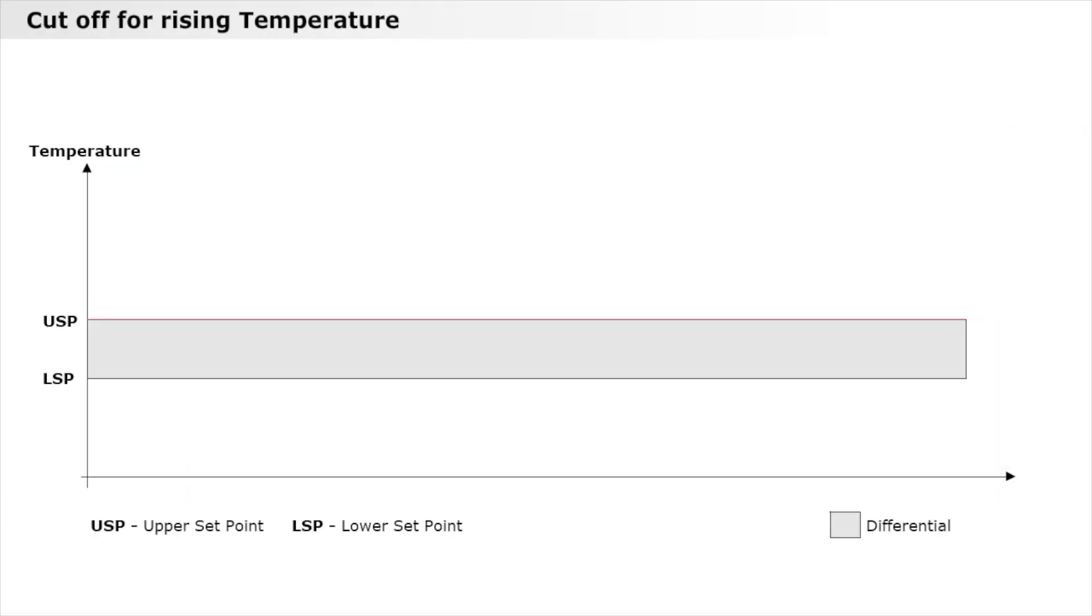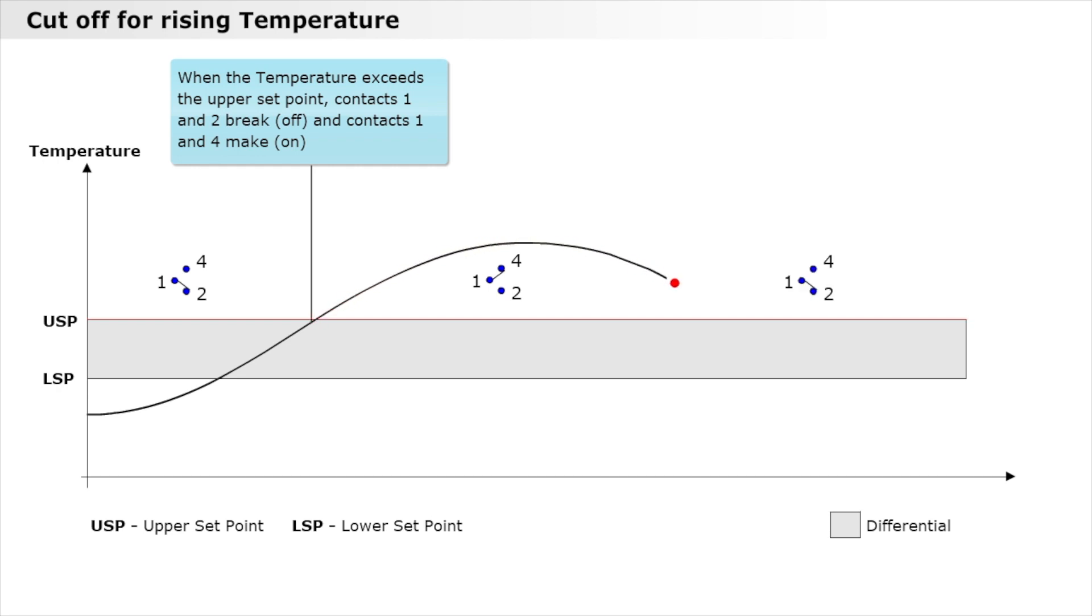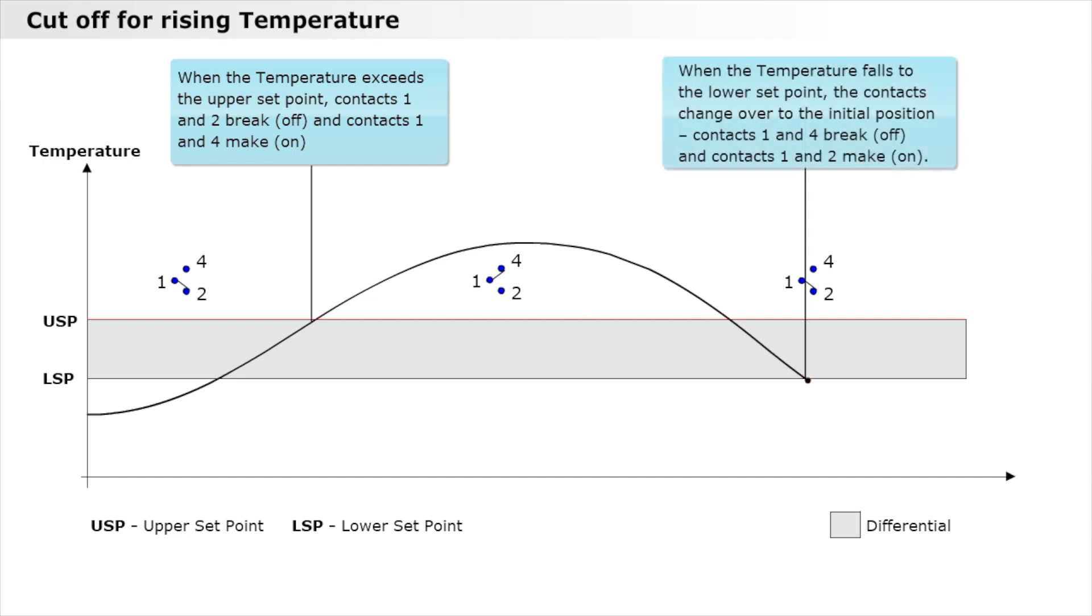Let's look at the cutoff for rising temperature. When the temperature exceeds the upper setpoint, contacts 1 and 2 break, and contacts 1 and 4 come together. When the temperature falls to the lower setpoint, the contacts change over to the original position. Contacts 1 and 4 break, and contacts 1 and 2 come together.